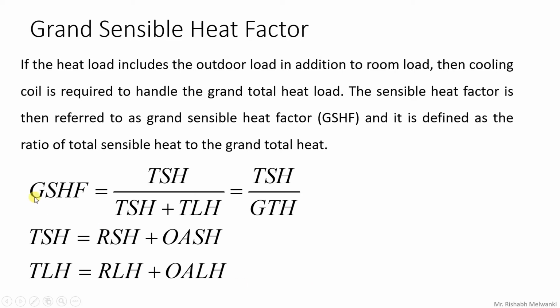Okay, so here I have written the equation of grand sensible heat factor. It is total sensible heat upon total sensible heat plus total latent heat. So this will be equal to total sensible heat upon grand total heat. Now what is total sensible heat? It will be room sensible heat plus outside air sensible heat. Okay, and what is total latent heat? It is room latent heat plus outside air latent heat.